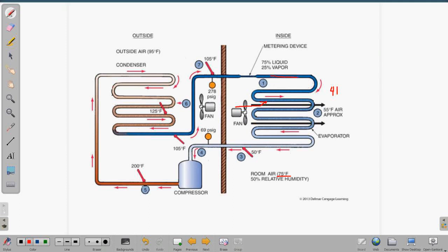So this evaporator coil is designed so that as the refrigerant travels through, it is changing state all the way through the coil to a specific point, which is designed by the engineers. So the first part of this coil right here is absorbing a tremendous amount of heat as the refrigerant is changing state, or boiling, into a vapor. At a certain point in the evaporator coil, just before the refrigerant exits the coil, it has changed state from its saturation point into 100% vapor.